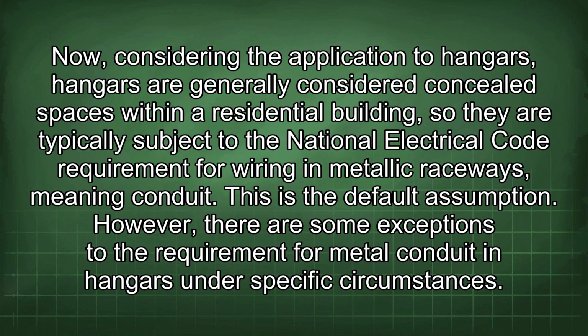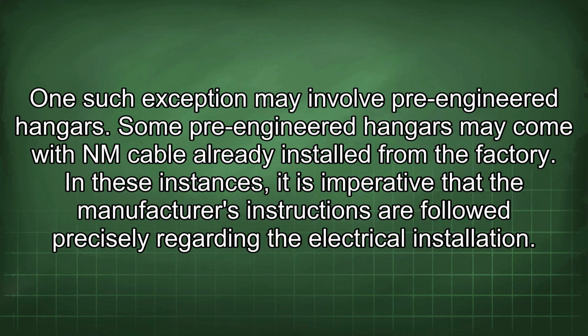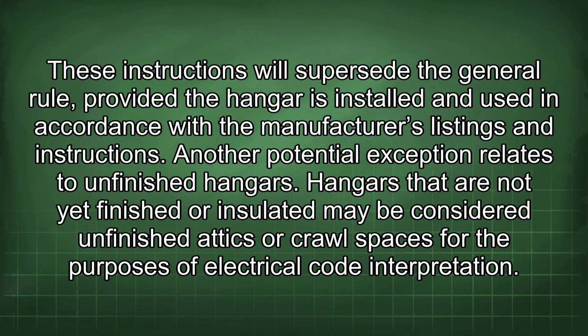However, there are some exceptions to the requirement for metal conduit in hangars under specific circumstances. One such exception may involve pre-engineered hangars. Some pre-engineered hangars may come with NM cable already installed from the factory. In these instances, it is imperative that the manufacturer's instructions are followed precisely regarding the electrical installation. These instructions will supersede the general rule, provided the hangar is installed and used in accordance with the manufacturer's listings and instructions. Another potential exception relates to unfinished hangars.